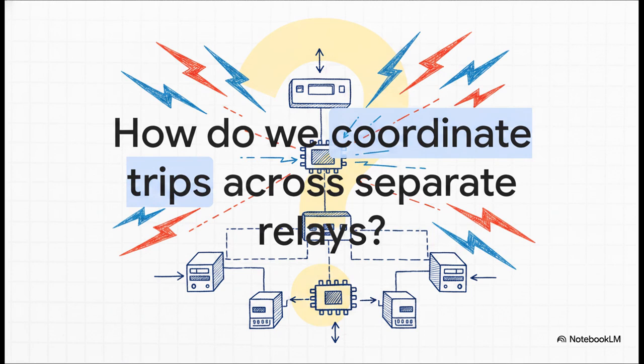So the absolutely crucial takeaway here is that by properly applying either low or high impedance REF, you've successfully deployed that dedicated close-up camera. You have secured the blind spot near the neutral point where standard differential protection struggles. But this raises a massive operational question. You now have differential protection watching the phases and ground fault protection watching the neutral. How do you ensure all these separate protection stages communicate perfectly and fire the exact right breakers at the exact right millisecond when a fault actually happens? Well, that requires a flawless master trip logic, and that is exactly what we're going to be decoding in our next explainer. Catch you then.